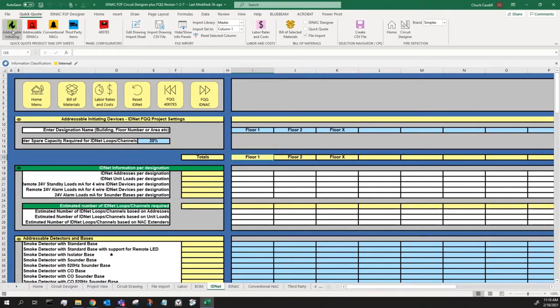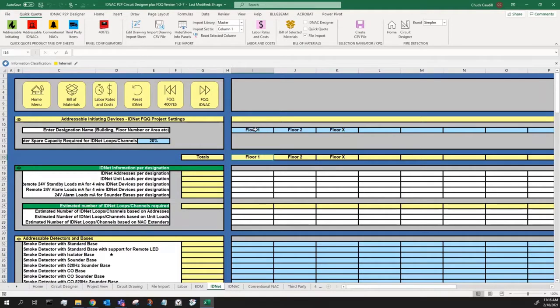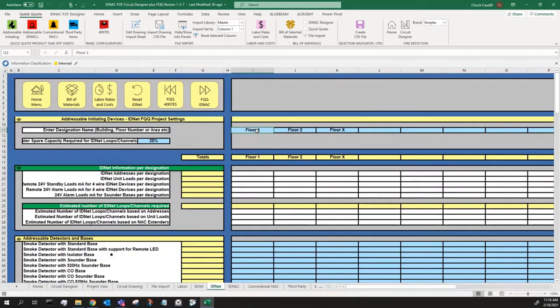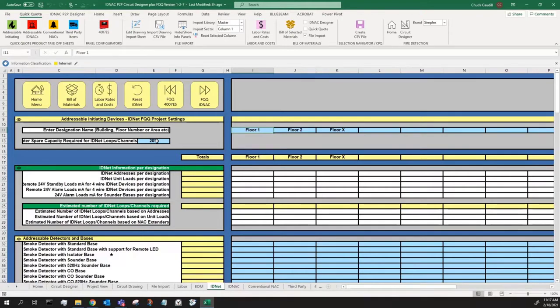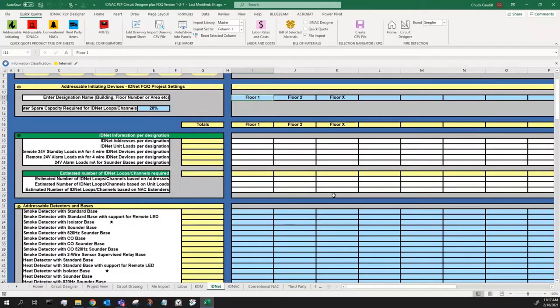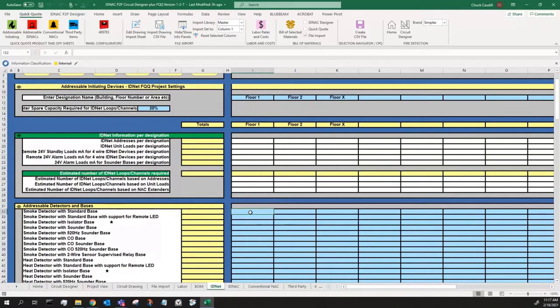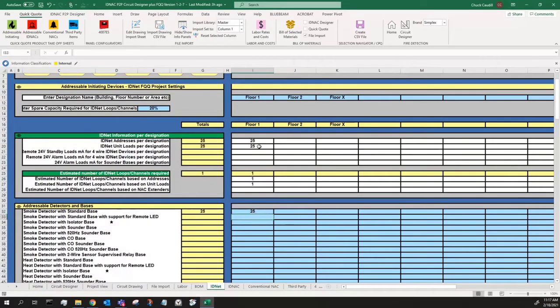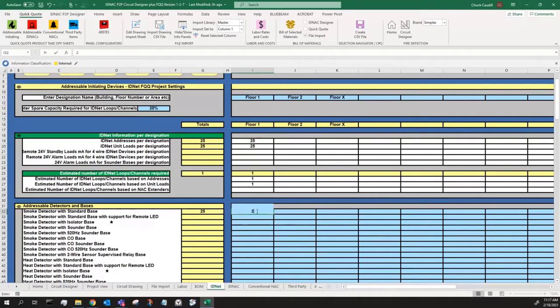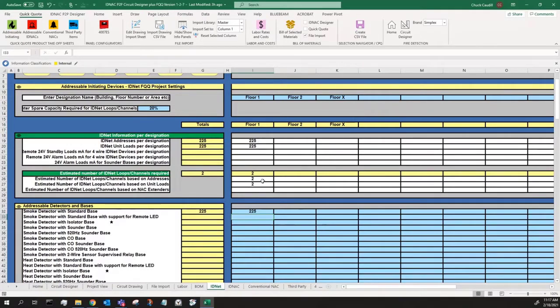The IDNet is the first one. Everything in light blue can be edited to fit your purposes. I can change the column header from Floor 1, 2, or 3 to Electrical Drawing E101, E102, E103. I can set my spare capacity. If I say I want 20% spare capacity headroom, you can only put 200 IDNet devices on the 250 points before it takes you to a second loop. The center section has your totals. Then the bottom has all of our IDNet devices laid out individually with their different option configurations. So the smoke detector with standard base is here. That's both the smoke and the base. You don't have to search for them separately. If I tell it I need 25, it automatically populates at the top with 25, and that will fit on one IDNet loop card. But if I go 225, it is giving me 225 addresses, but that has to fit on two IDNet loops.